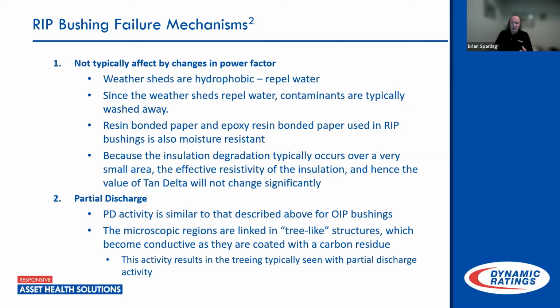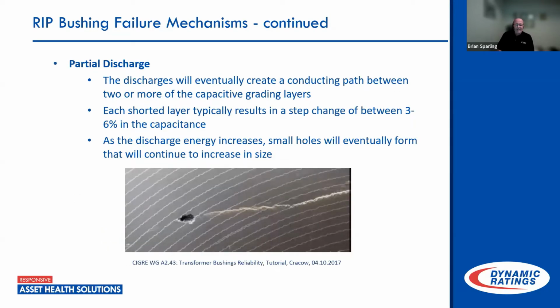But the insulation system degrades over time. Usually in a very small area, it can start with a void. Partial discharge can develop inside, again following the manufacturing process, if there are minute voids left in the construction of the bushing itself. Part of that Cigre study, and if you are a Cigre member, you know how to get a copy of this. It's free to Cigre members. However, if the guide is more than 3 years old, you're able to go into the Cigre website and obtain this brochure for free. All they want is your contact information.